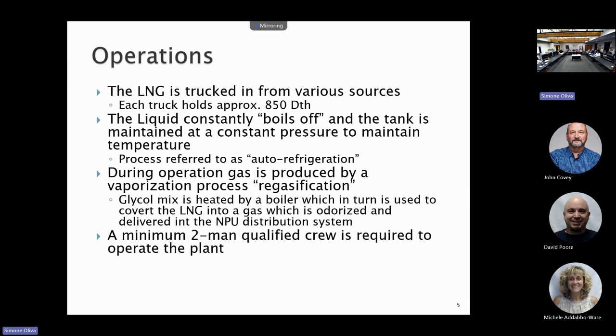The liquid is constantly boiling off. I mentioned that a little bit. That's how it maintains temperature inside the tank. That boil off gas then gets warmed up, odorized, and sent out into our system. It's kind of a byproduct of what we have, but it has to happen in order to maintain that temperature without mechanical refrigeration. This process is referred to as auto refrigeration. It self-cools by boiling off and maintaining the temperature inside of the tank. I was going to ask a question, but you went and answered it. So all the gas that boils off from the tank goes back into our system, back into the distribution system. Okay.